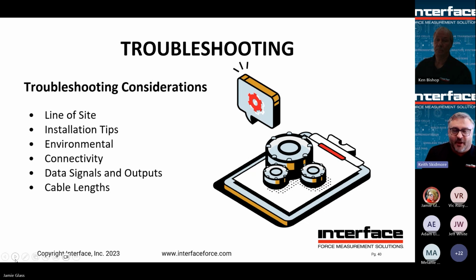that are reading them. Cable lengths can be an issue. You have long cable runs and say they're out in the sun, the temperature changes, the signal basically changes due to temperature, and you can get drifting, and you think it's problems with the device, but it's really temperature sensitivity. And so that can be mitigated by, say, running the cables in troughs, or insulating them somewhat, or maybe using wireless, or changing the position of the equipment so you don't have as long a cable run.